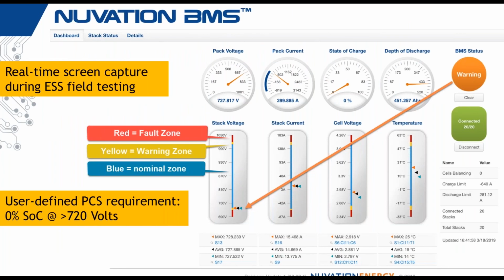And so we've got a screenshot of a real system here where the PCS had a requirement of 720 volts minimum, but the battery system can go down to 700 easy. And so in this case, even though those safety thresholds might be set there, we're defining our 0% SOC. We're defining our warning zones according to the system.